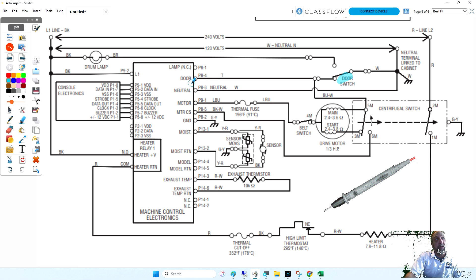L2. Not L2. L2 is only for the heating element. L2 is here only for the element. The motor runs off of neutral and line 1. The board lights up, so we know neutral's good. We know line 1's good. We said the door switch could be bad if I don't have power on these two pins. But what is physically missing from this schematic that the machine has?